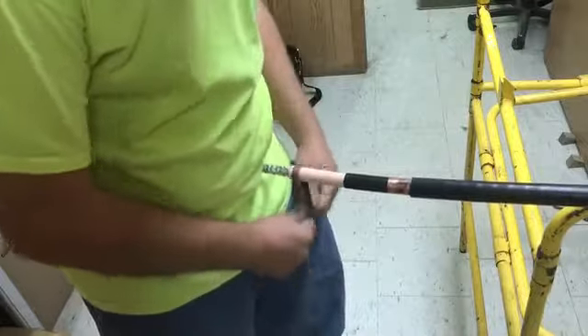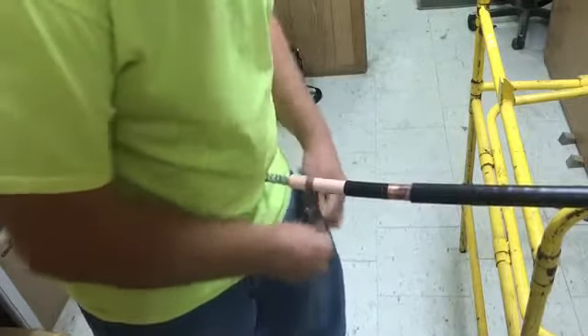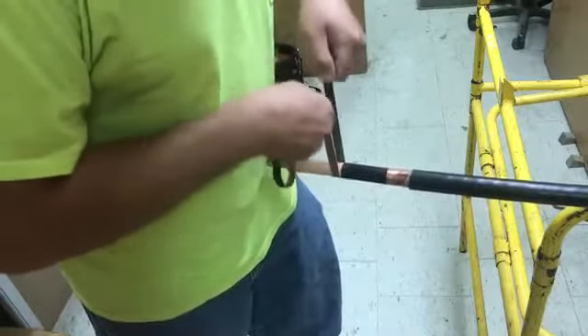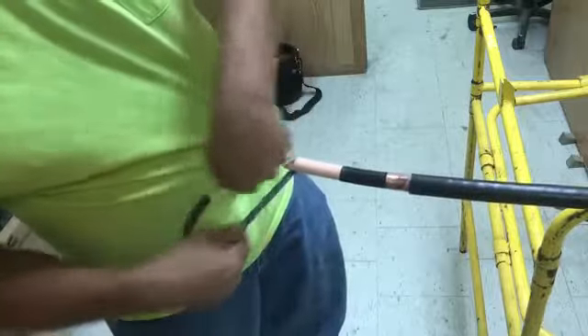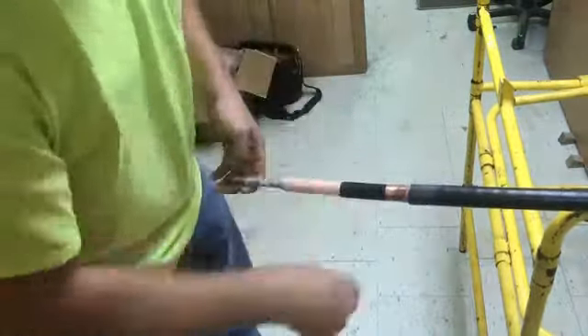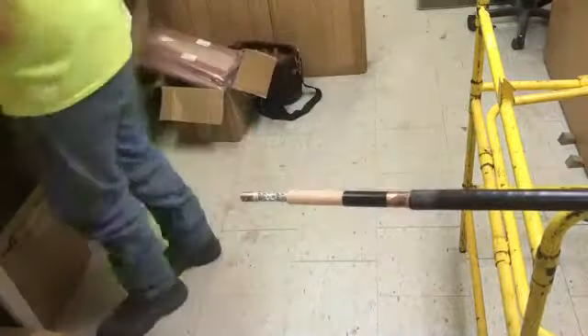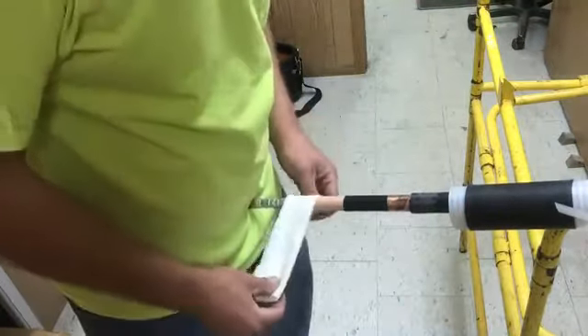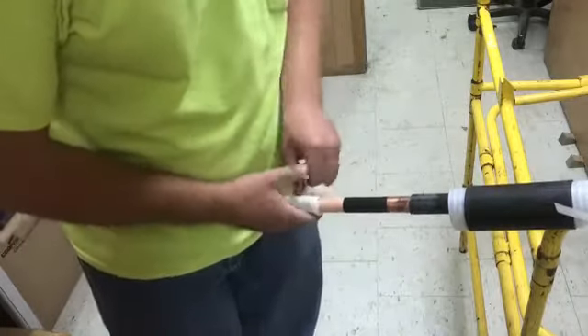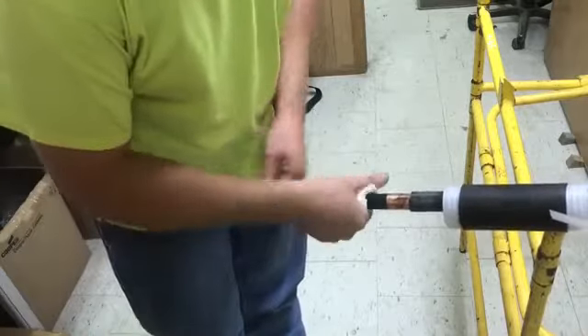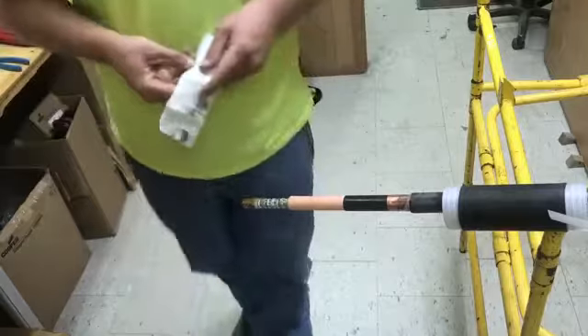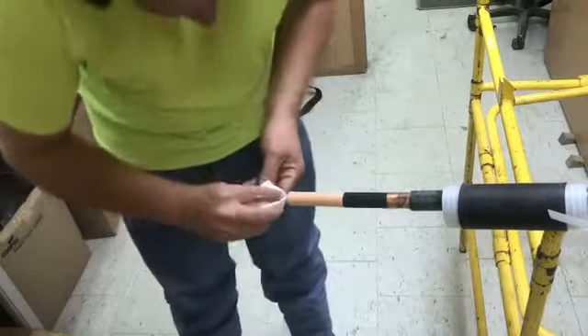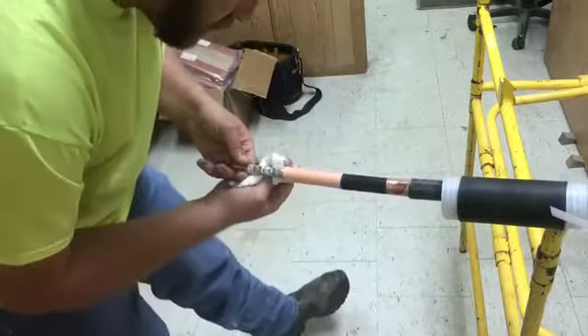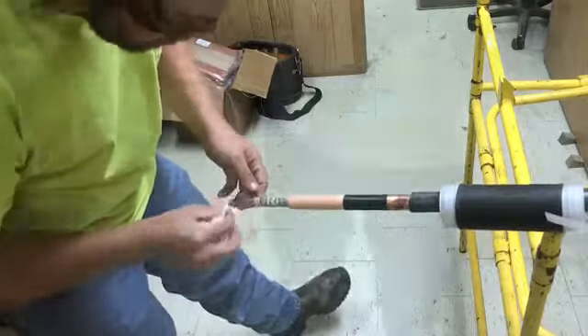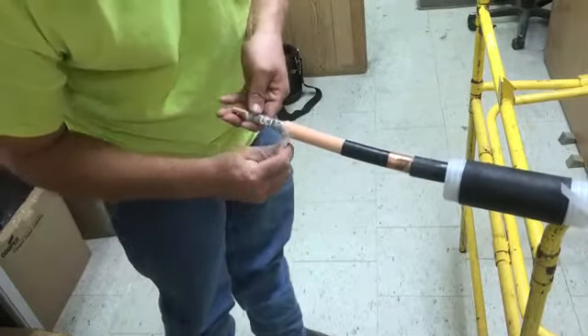Using the 120 grit sandcloth, I will now sand the cable evenly on all sides. I will now nest the cold shrink tube before I clean the cable and install the termination. Using cleaner and a wipe, I begin at the end of the cable and work my way back to the semiconductive layer. I'll now apply silicone grease to ease the installation of the termination.